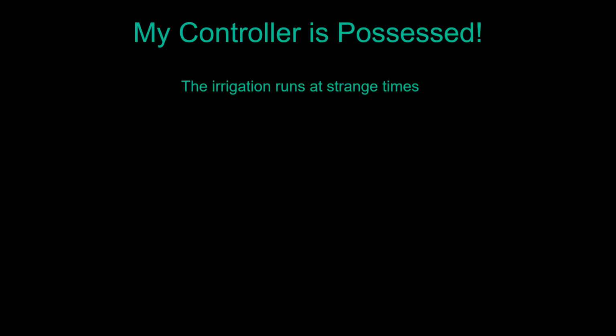Another good one is the irrigation runs at strange times. This also could be a programming error. The displays on those controllers very often are very small, and it's hard to see the difference between AM and PM. But if you get those mixed up, either with your current time or a start time for a program, it's going to come on 12 hours different than what you thought it was.